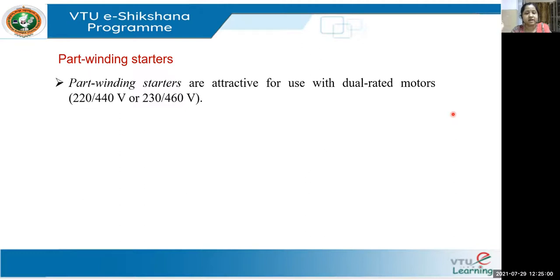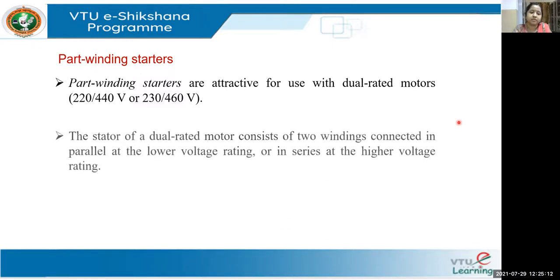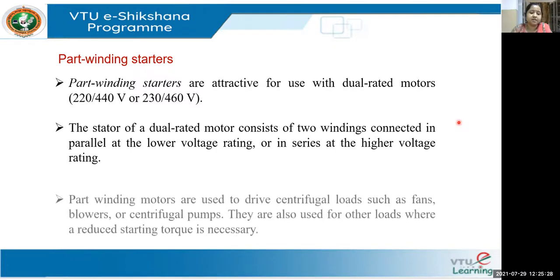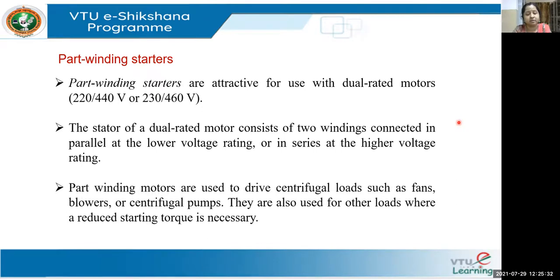Part winding starters are attractive for use with dual rated motors — motors that can run at 230V as well as 460V. The stator of the dual rated motor has two windings that can be connected in parallel for lower voltage or in series for higher voltage. Part winding motors are used to drive centrifugal loads such as fans, blowers, and pumps, and are also used in air conditioning systems.